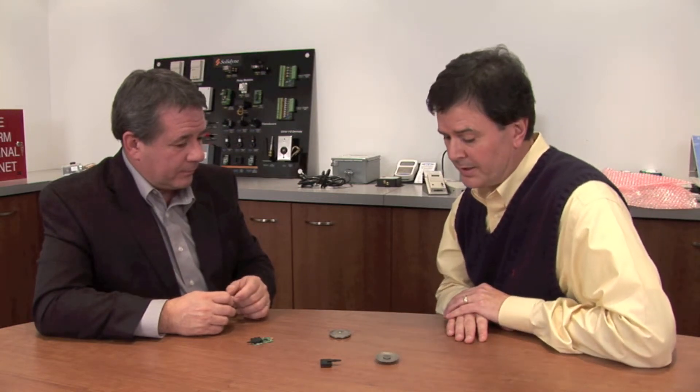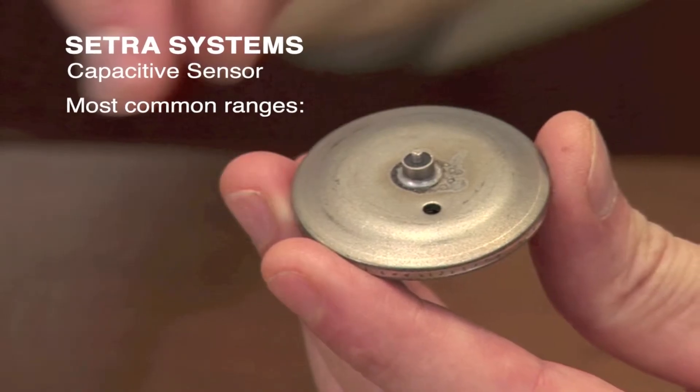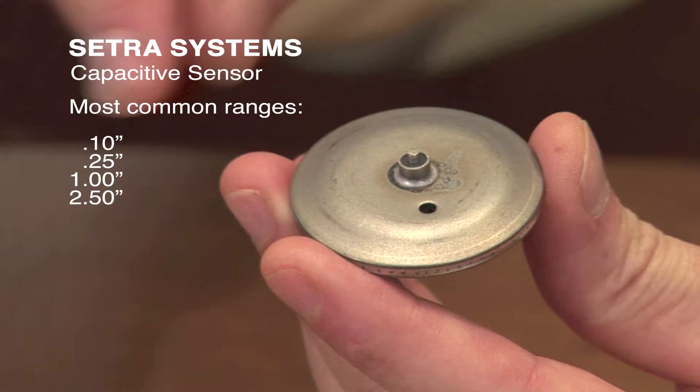The bulk of the sensors we sell are single-range sensors. But your competition sells multi-range, multi-output sensors. What's the compromise there? Well, let me give you a little background on the sensor Setra has been making for almost 40 years. We make ranges as low as a twentieth of an inch, all the way up to 100 to 150 inches. The most widely used ranges are tenth-inch, quarter-inch, one inch, two and a half inch, three inch, and five inch. The electronics use the same package looking for the same basic change in capacitance on each sensor, no matter what the range is.